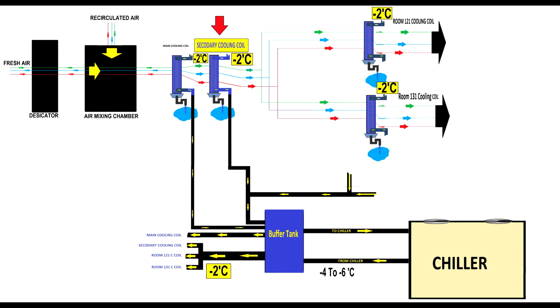Here we did some modification to the system. We converted the heat exchanger into a cooling heat exchanger, and we raised the glycol temperature a little bit, hoping to avoid the icing-up phenomenon. But this is just a project. We didn't do this project yet. We are working on it. We have to do some calculations.